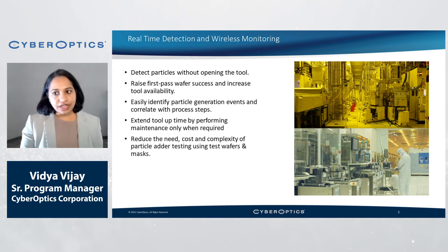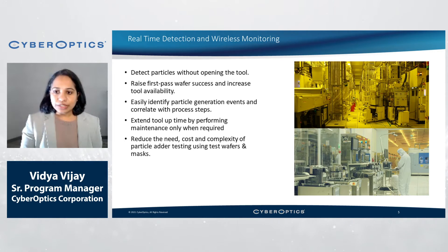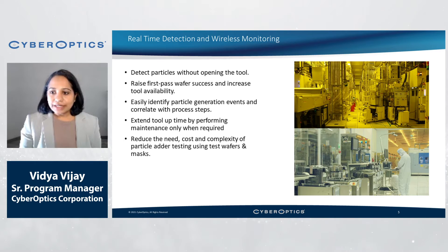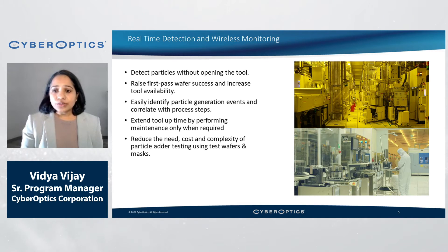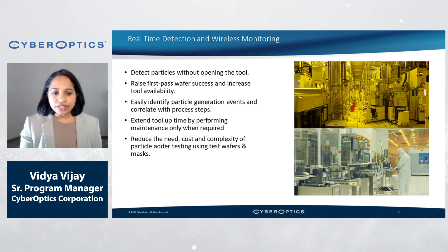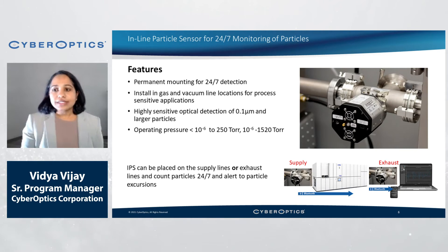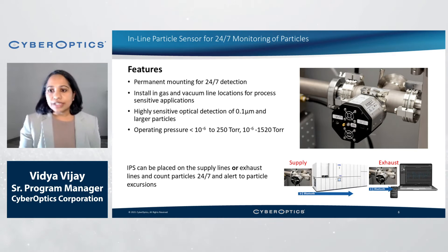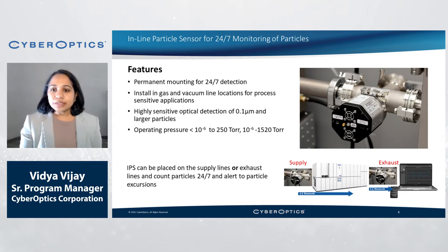If we can detect particles in real time and do so wirelessly, we solve many concerns in the semiconductor environment. We do not have to open the tools to make such particle measurements. Once we identify the source of contamination at a particular process step, the tool uptime is increased by performing maintenance at the required area, increasing first-pass wafer yield and tool availability. We can also reduce the cost and complexity of using test wafers and reticles. CyberOptics has developed a sensor that can detect airborne particles in vacuum and gas flow lines. The IPS is permanently mounted in the supply or exhaust line and detects particles 24-7.